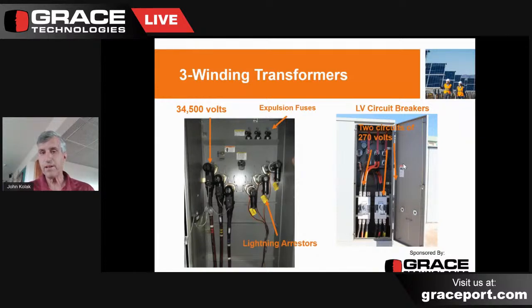If you look in the top part of the slide, you'll see there are three what we call well-type fuses. Those are expulsion-type fuses, and we're going to talk about the differences between expulsion fuses and current-limiting fuses in just a moment. But what's interesting about this is you can actually change those fuses. So from the engineering standpoint, this does give us the opportunity to refuse the current characteristic curves. So we can actually sometimes lower incident energy even on the output of the system by changing the fuses in the transformer. Normally, the expulsion fuses in a pad mount transformer are under oil in the tank. They're actually sitting on the bottom of the tank of the transformer, and you can't do anything about them as far as changing them. Solar farms especially often have these well-type fuses, which gives us choices from the engineering side.